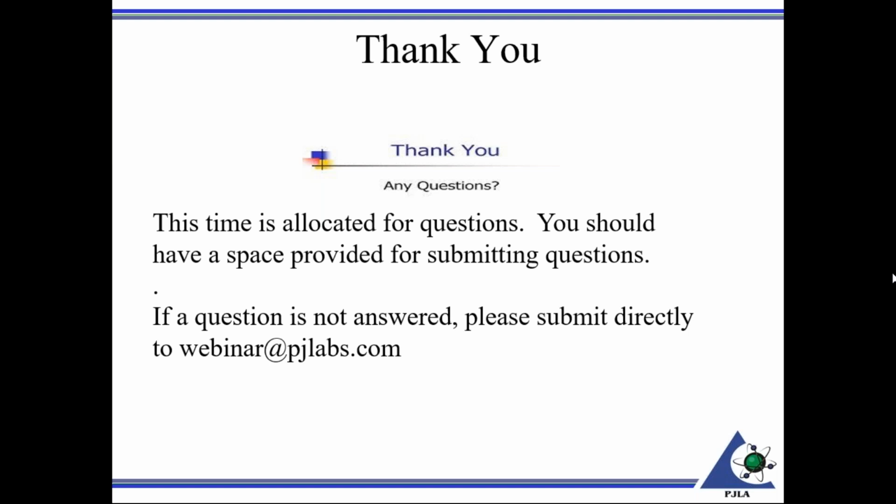So I don't know if you have a preference for a specific make or model or whatever. I don't think that would be considered appropriate to be put on a calibration report unless the results are telling you otherwise. So again, that's 7.8.7. And so I'm just speaking on behalf of the requirements of 17025. If you want to have a conversation with your customer about the specific issue, then under 7.8.7.3, this is being communicated with dialogue. You could keep it away from the report. However, just maintain a record of that dialogue with the report.